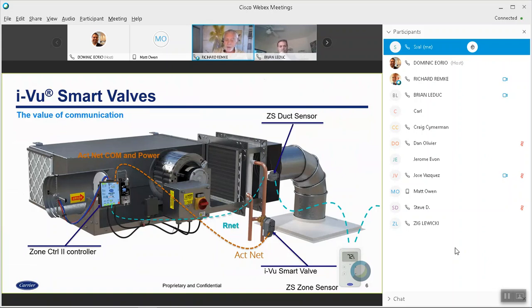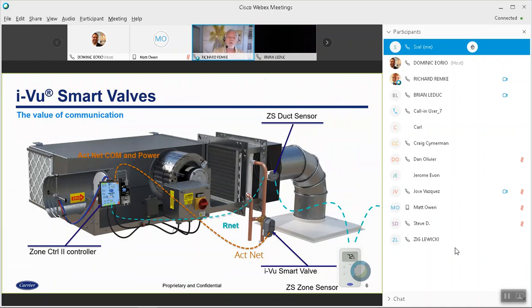because what happens is this frees up the I/O that you were using for the valve to be used for something else. So now you get some extra I/O in the controller. If you look at an application where you're using the RNet sensor for maybe a duct sensor and maybe a space sensor, and the Act Net network, you haven't used up any I/O yet on that programmable zone controller, and so you get more capabilities in the zone by using the Act Net communication network. And one of the cool things is that 3-wire connection to these valves is not only communication but also power to the valve too. So you don't have to worry about installing a separate transformer and running power to it. You just run it right to the controller from that 3-wire connection.